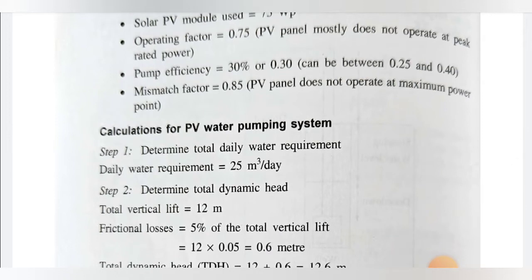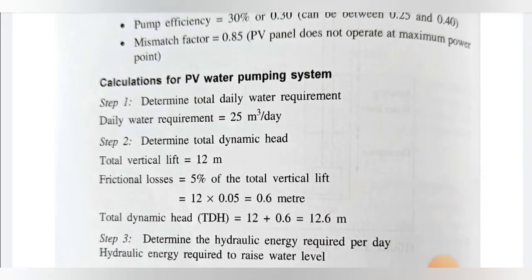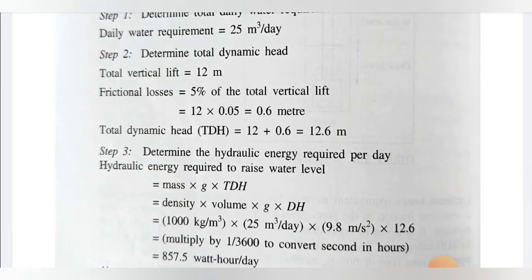Step 1: The total daily water requirement is 25 cubic meters per day. Step 2: Determining the Total Dynamic Head (TDH) — TDH equals vertical lift plus frictional losses. Vertical lift is 12 meters, and frictional losses are 5% of vertical lift: 0.05 × 12 = 0.6 meters. Therefore, TDH = 12 + 0.6 = 12.6 meters.